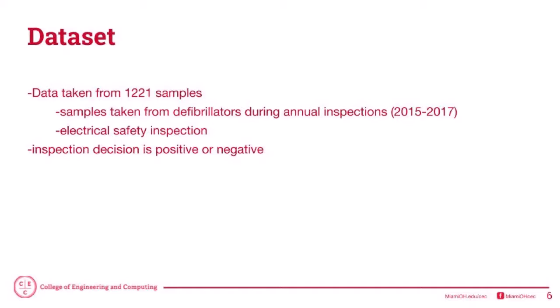And the samples consisted of 7 features: defibrillator output energy measurements, result of the safety inspection, device age, manufacturer, type, and information about preventative and corrective maintenance and inspection decision. Then each sample had 38 features. There was also an electrical safety inspection that was performed according to the IEC 60601 medical electrical equipment electrical safety standard. So this measured the mains voltage, protective earth resistance, insulation resistance, earth leakage current, enclosure leakage current, and patient applied parts leakage current. And then the inspection decision is either positive or negative.